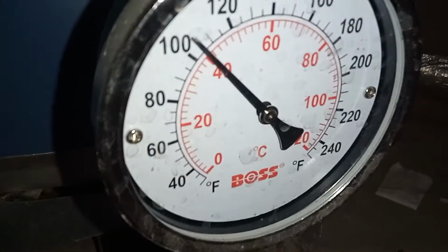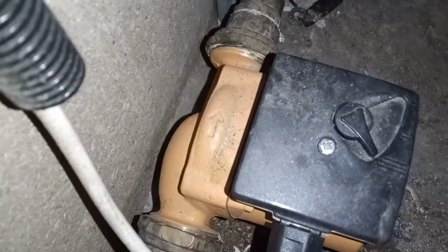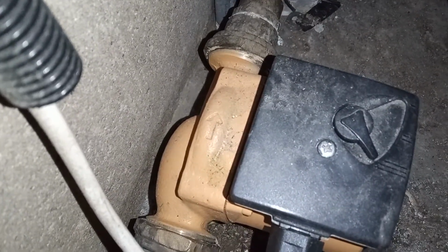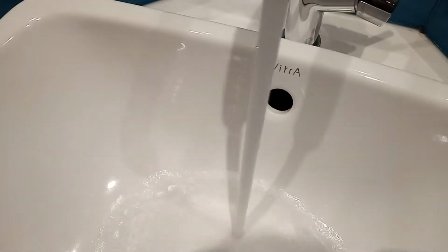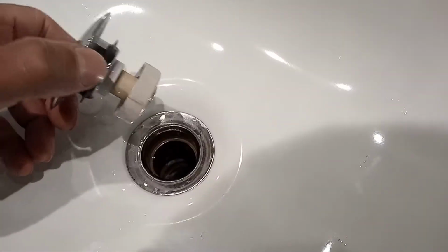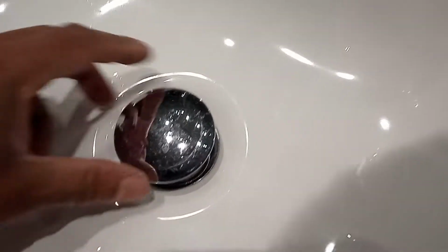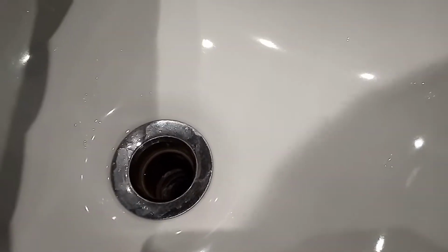We have good hot water return temperatures. Here's our return pump. So this is one of our rooms where we had really bad flow rate, and as you can see it's a lot better. Always remember to remove these if you're ever doing any tap flushing or leaving the taps to run, because you don't want them to overflow. You can't trust the overflow.